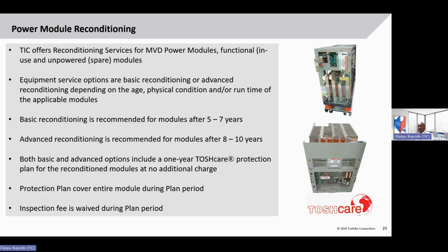The options available are basic reconditioning and the advanced. And what level of service applies will depend on factors such as the age, the physical condition, and or runtime of the modules. A module that's 10 years old but not run, maybe run only once a week, might require a different service from one that's run 5 years, but it's 24/7 operation in the cement plant. So these recommendations are general, but it could be specific recommendations based on your specific situation. So in general, we recommend the basic reconditioning for modules after 5 to 7 years, the advanced after 8 to 10 years in operation.